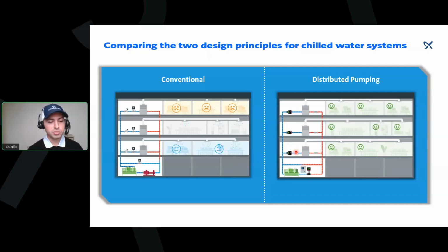Okay, so now you're reducing that. Why do we do that? Now you have free flow in your system, right? They're self-balancing. Now you can reduce that head significantly. Now you're going to go from a much bigger pump system to a much smaller one, because all your pump really needs to do is basically, as people say in the industry, keep that chiller happy, right? You're just delivering minimum flow here for that chiller.